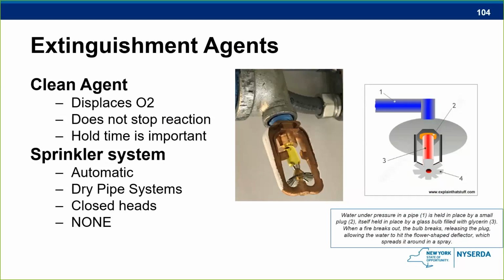So we wanted dry pipe specifically for outdoor installation. For indoor installations, you probably won't have that. That's going to be an automatic one. Plus, if it's also on a rooftop, you may have automatic. So that's something that you're going to have to take a look at and make your decision on. As I said before, they're going to be closed heads inside there. And in some remote locations, they won't have any extinguishing agent.